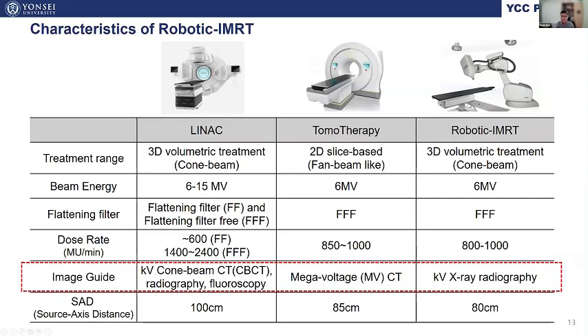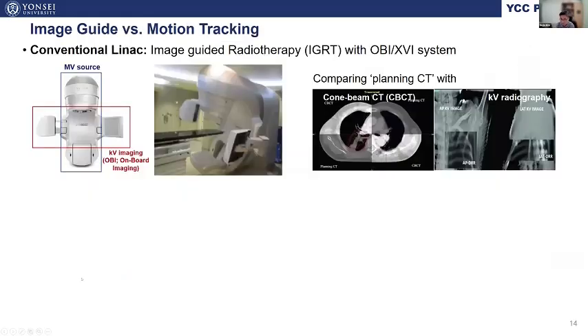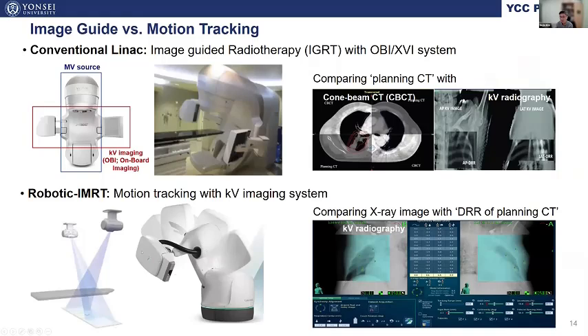The table in this slide compares robotic RT against the conventional linear accelerator. As seen in the red box, CyberKnife has a unique image guidance system. Conventional LINAC usually provides volumetric X-ray CT images, but robotic RT doesn't. Instead, it offers 2D kV X-ray images acquired at plus/minus 45-degree angles, which are compared against the DRR images produced from the planning CT images for image guidance. This seems problematic with respect to the accuracy of image guidance, but the simpler, the better and more powerful, especially when it comes to real-time motion tracking.